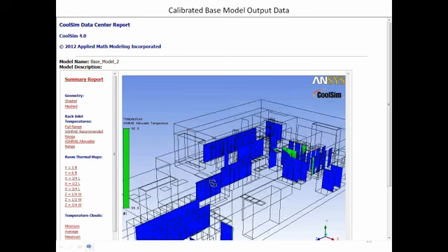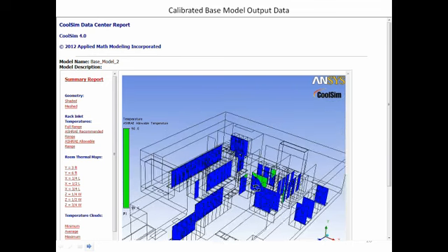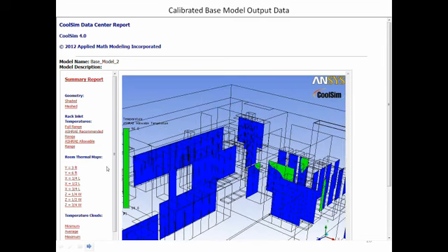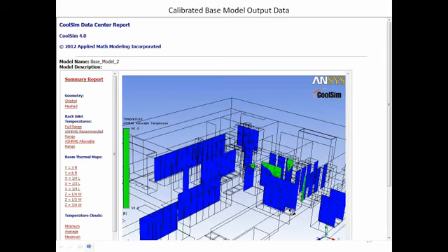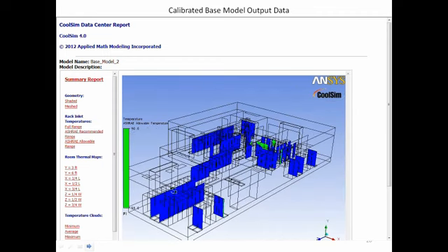We also have one which is allowable. The allowable gives that range a little higher, 59 to 90 degrees. And you see here that some racks are beginning to come into range on the allowable. We can change these, make these anything at any time, but I think it's a nice way to look at a plot and see whether or not it's within range.